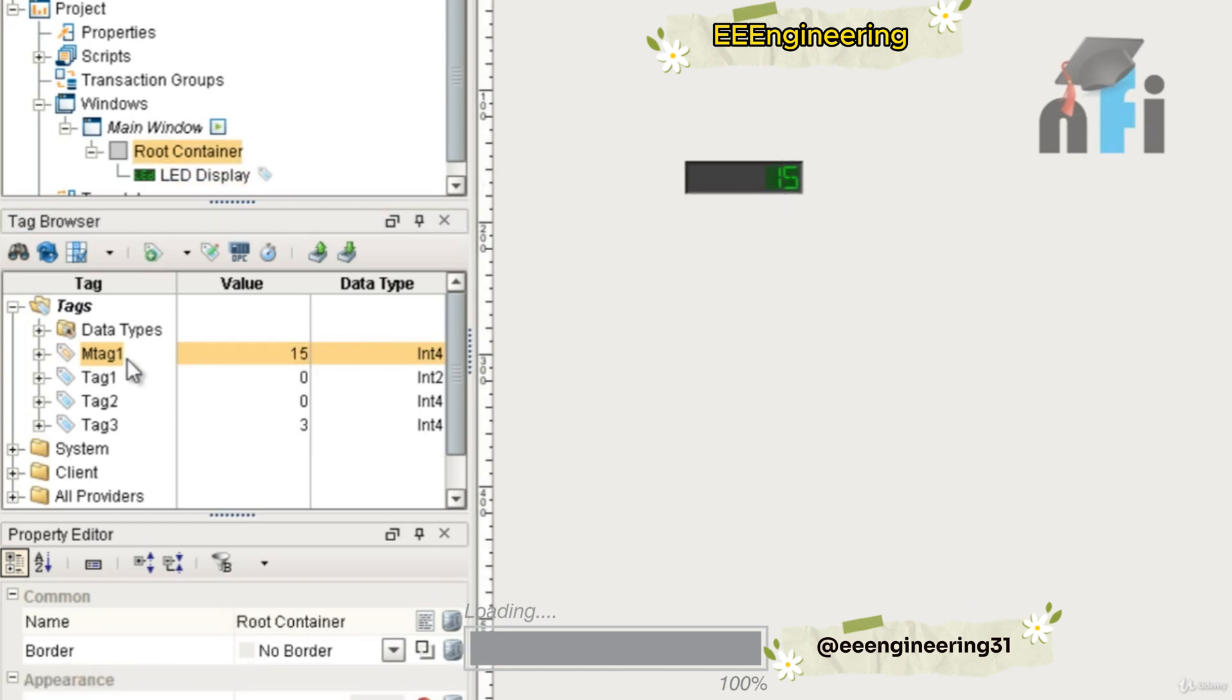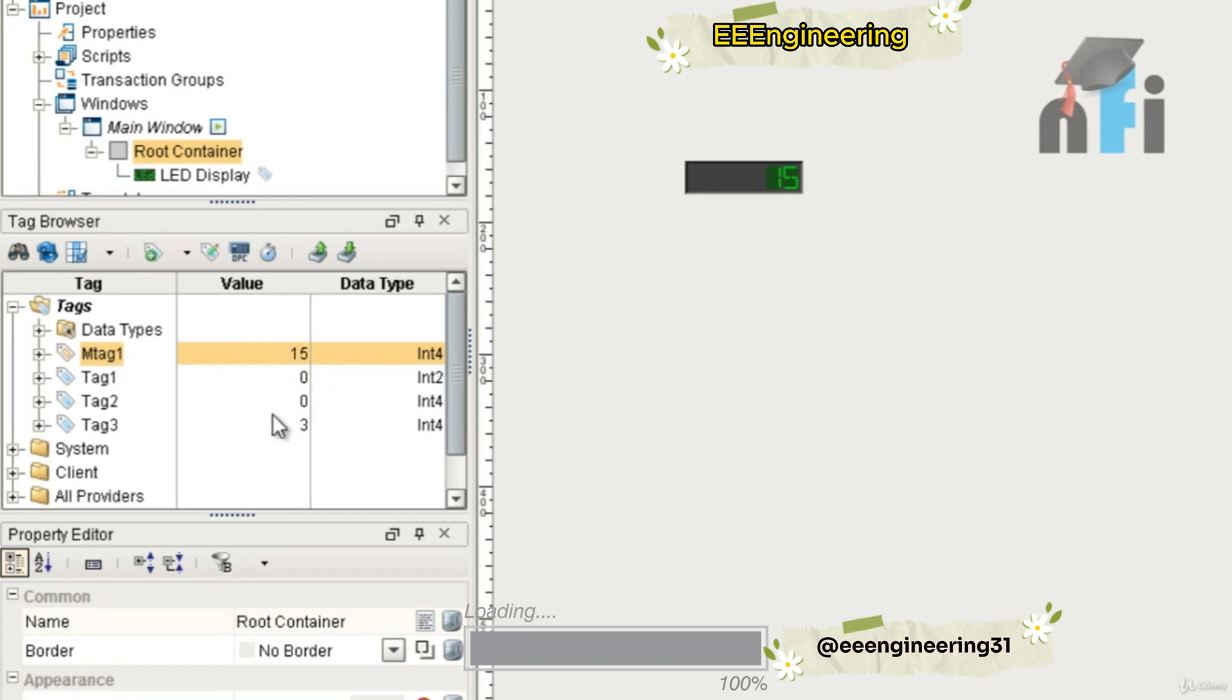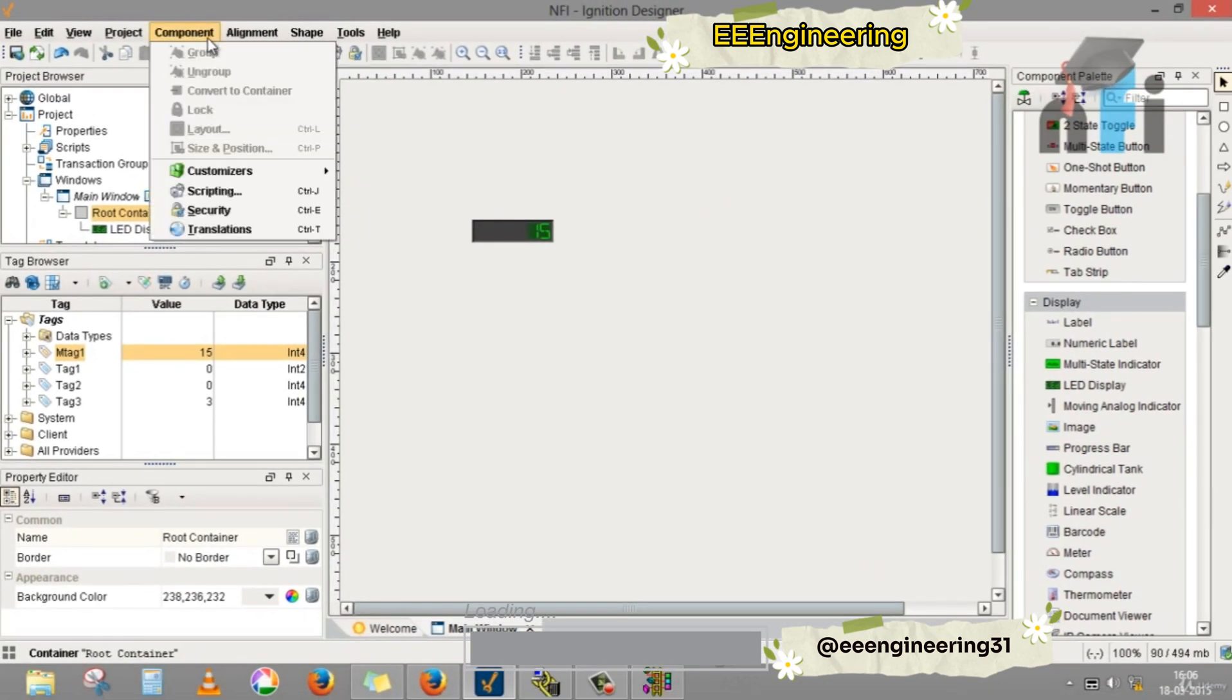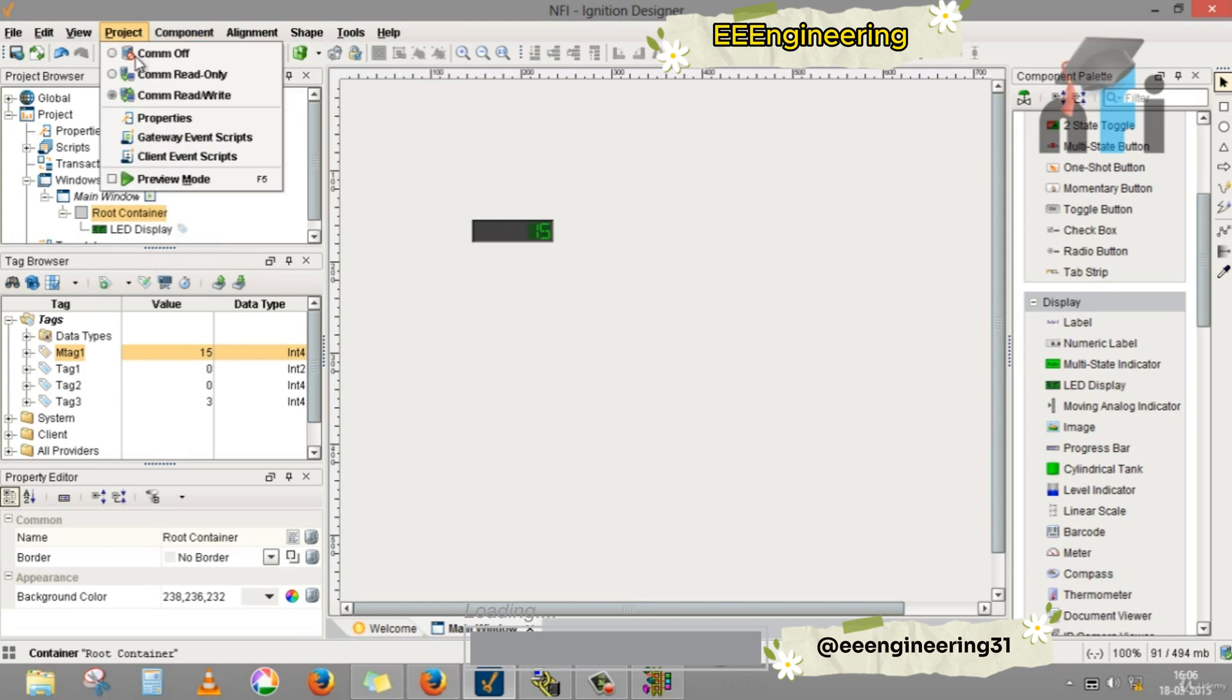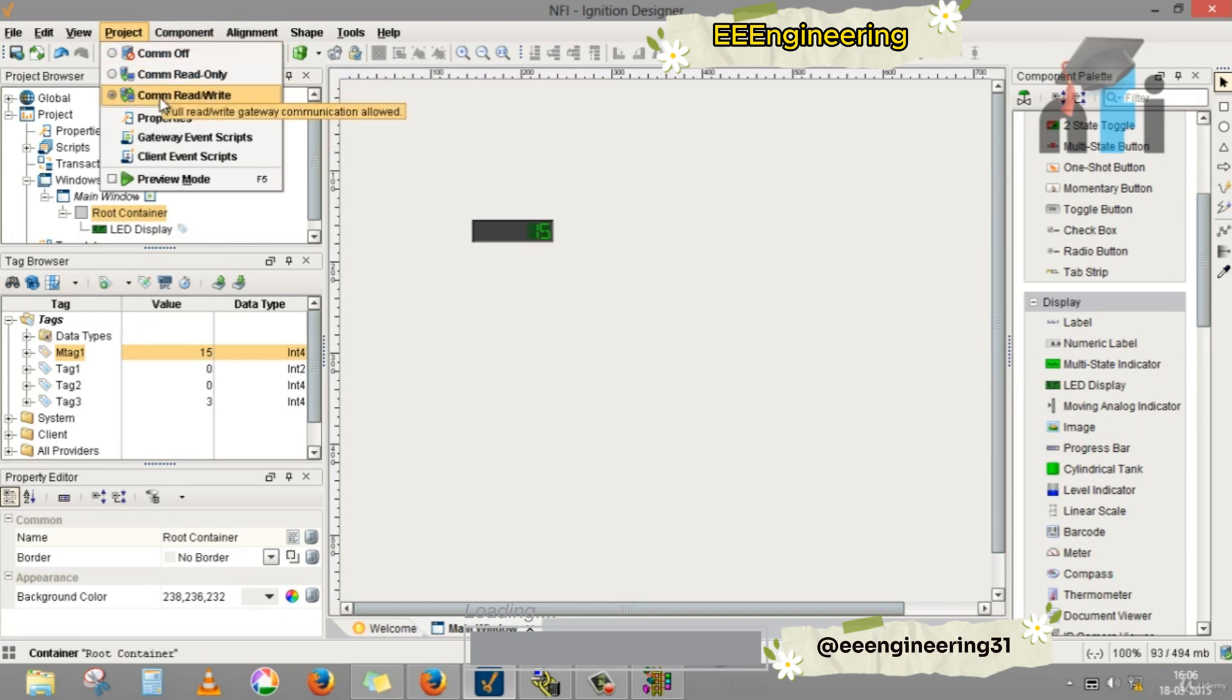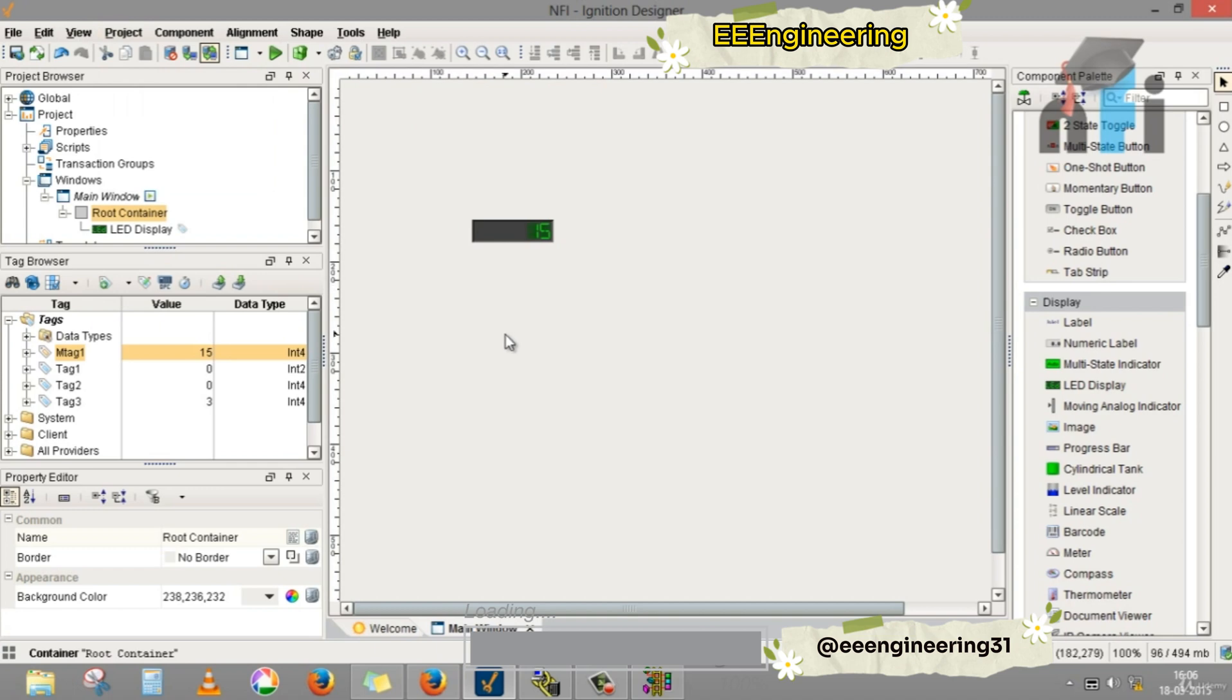These are the different tags. Memory tag and OPC tag. OPC is to read the information from external world. Memory tag is you can change, read and write information inside this tag section only. To enable read and write operation, you have to make sure your project is at communication read/write. If it is only at read-only it will not write the values. If it is at off it will not read or write the value. You have to make sure it is on communication read/write. This was about the tags.